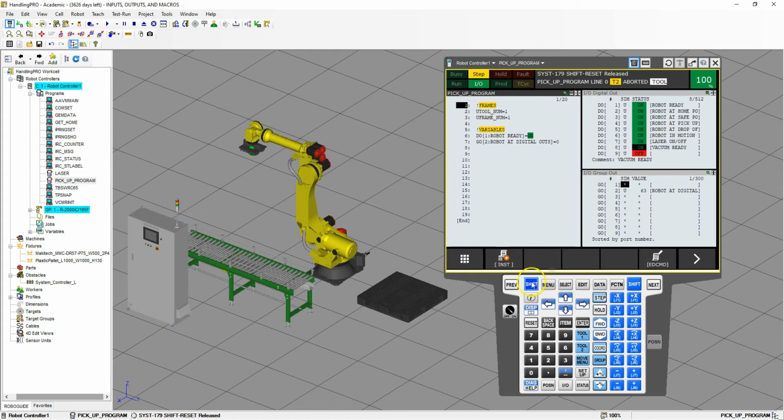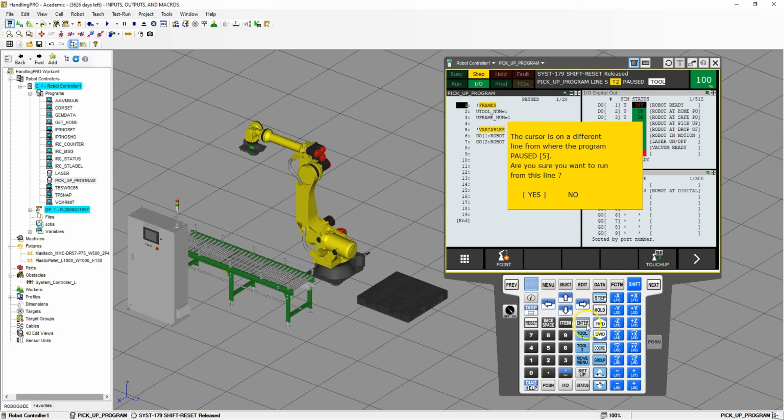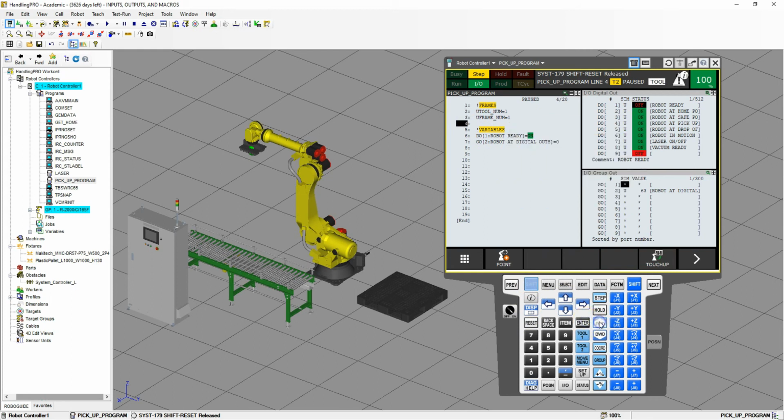So if I go step mode, shift forward, the first thing you're going to see is the digital output number 1 turn off, or turn on. So let's go in here. Let's turn this off to start out with. So I have it off, and let's go back in here, shift, step mode, go in here. So the first thing you're going to see inside here is that this is going to turn on. There we go, turns on, and then lines 2 through 8 should turn off. There we go. Oh, forgot number 8.